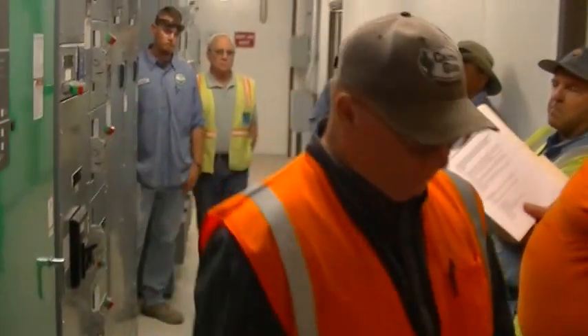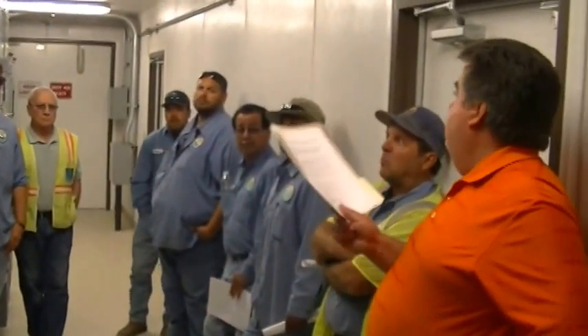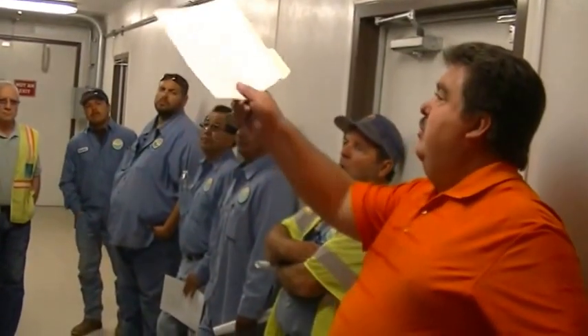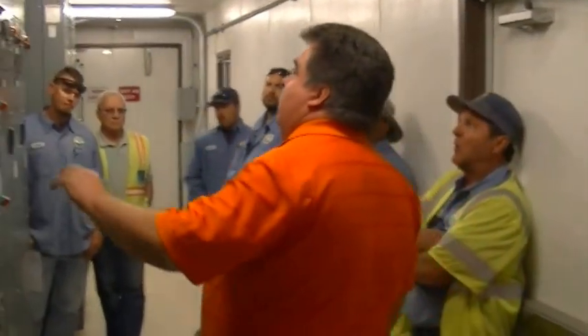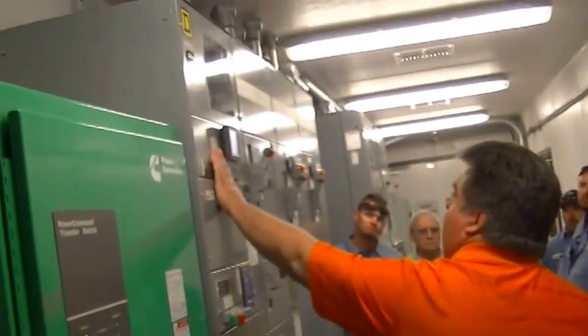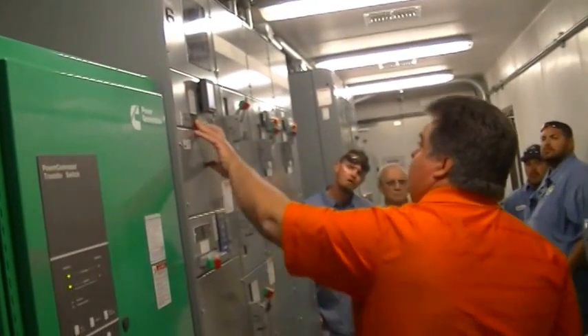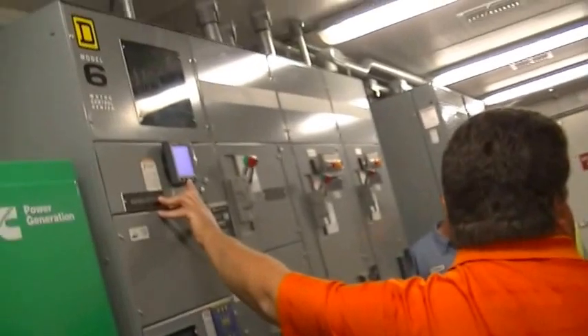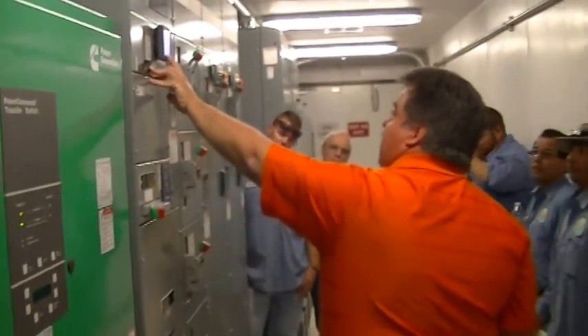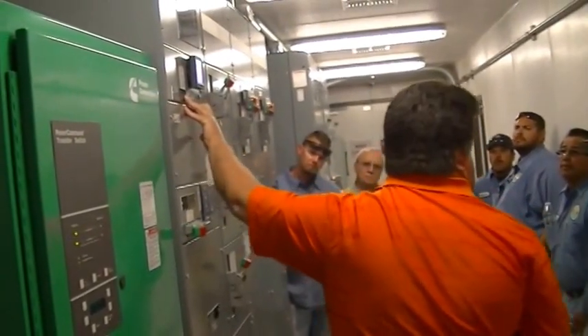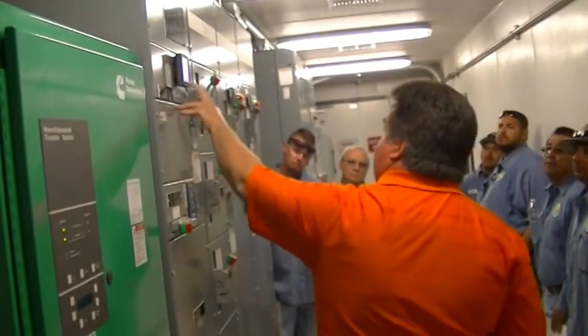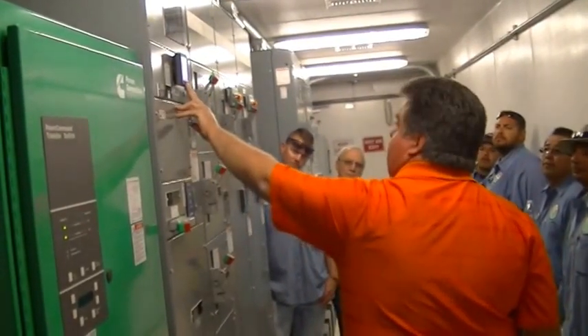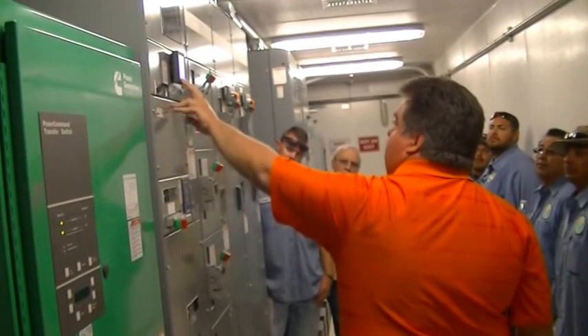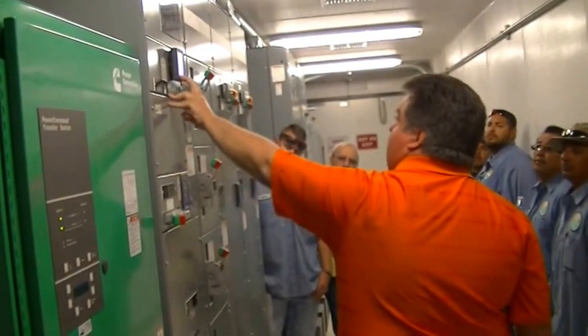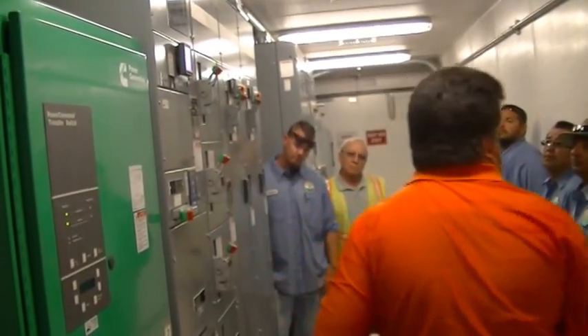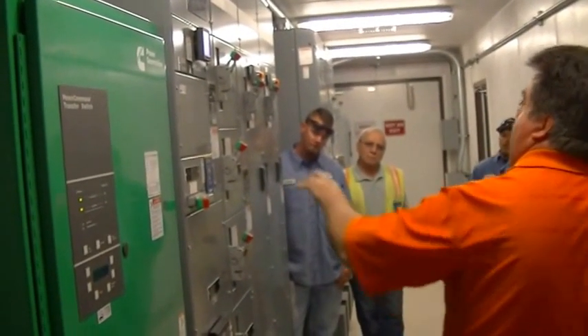Okay, so your power comes in, and it's best to just look at it from left to right. So your incoming power is coming into your MCC here, and this is a power meter. You can go through this power meter and just push buttons. So if I want to take a look at my voltages on my three phases, it says volts right here, and I push that button. And if I want to come back and take a look at my amps, there's your amps for the three phases.